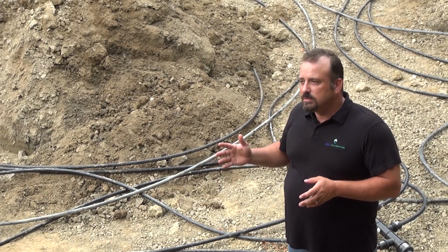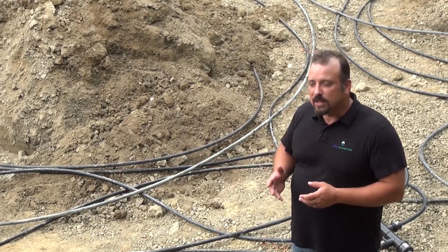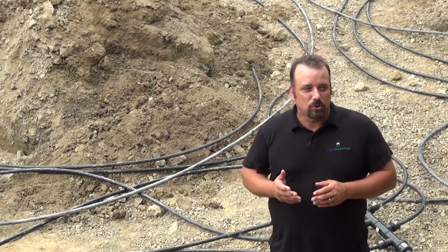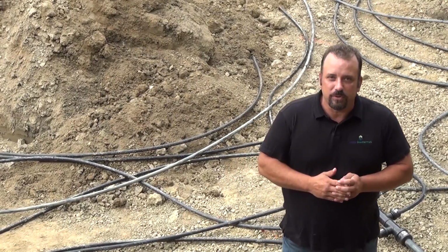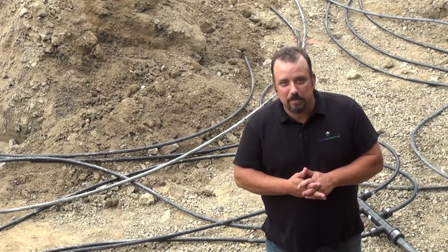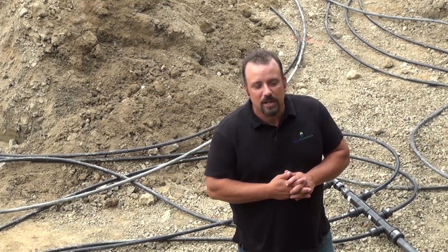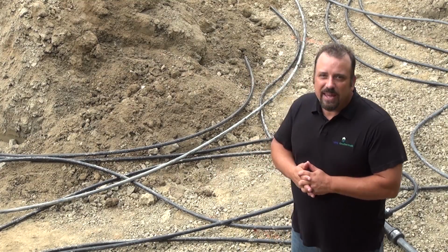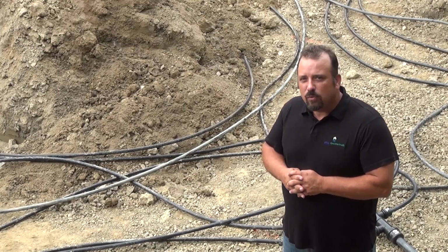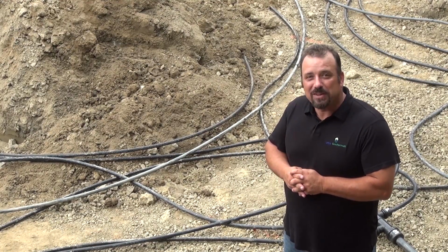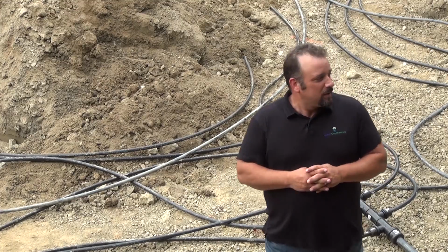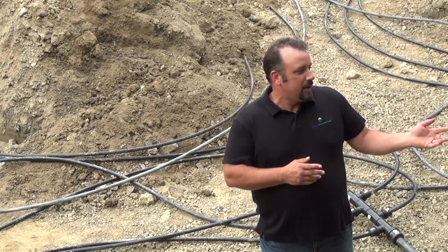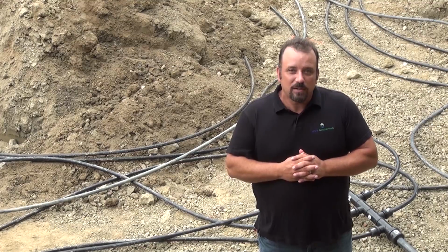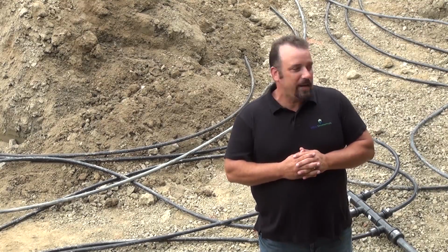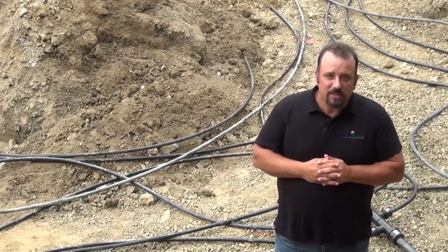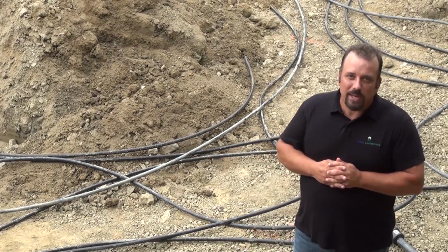If you don't have a piece of property that allows this, your choice would be to go with a drilled vertical closed loop system. This application had plenty of land mass, so they were able to do it very easily. It took roughly 2.5 days to excavate, and about a half day for the guys to lay the loops down and put everything together. Everything is tied into the building, and as we speak, they are pressure testing and doing a hydrostatic test with water and air to make sure there are no leaks. Off in the distance, the excavator is standing by, waiting to backfill.